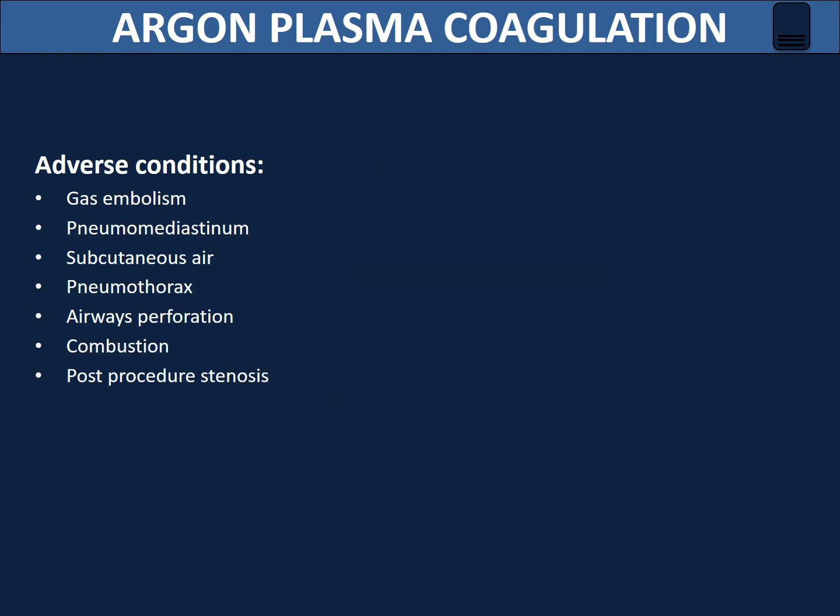Complications are more often related to faulty connections and operator error rather than the malfunction of the unit itself. Most of the complications described here can be avoided by working under visual control, avoiding direct tissue contact with the APC probe, using as low an argon flow as possible, not applying gas too long over the same anatomic location, and ensuring the supplemental oxygen level is below 40%.